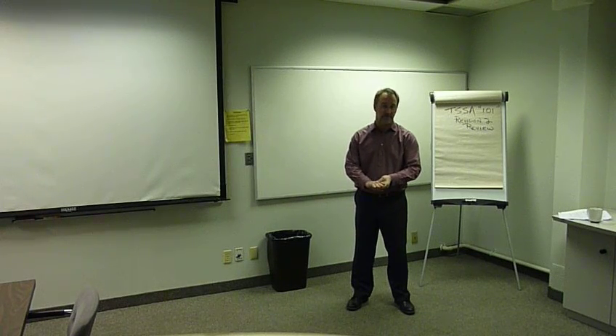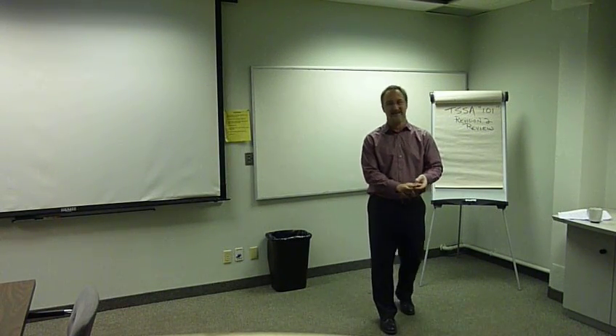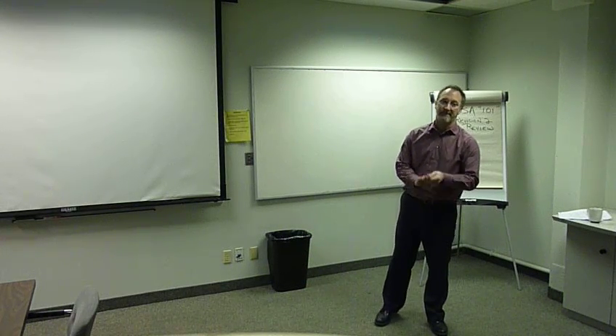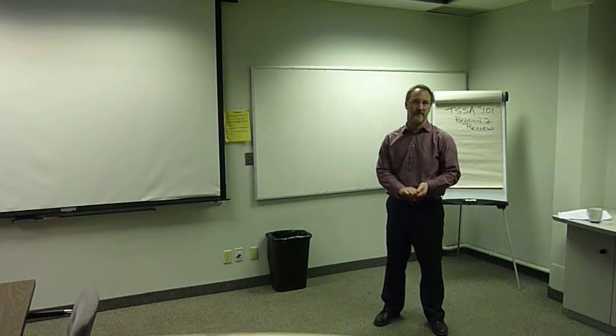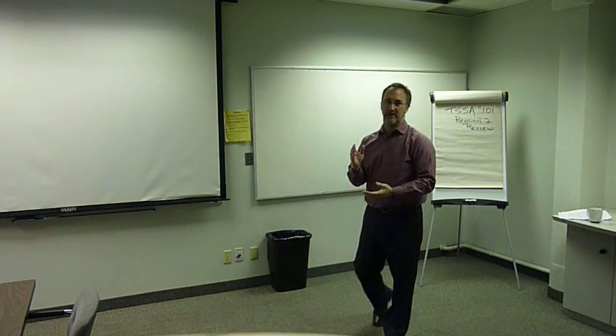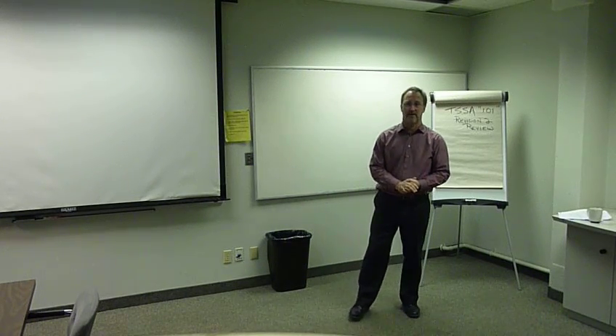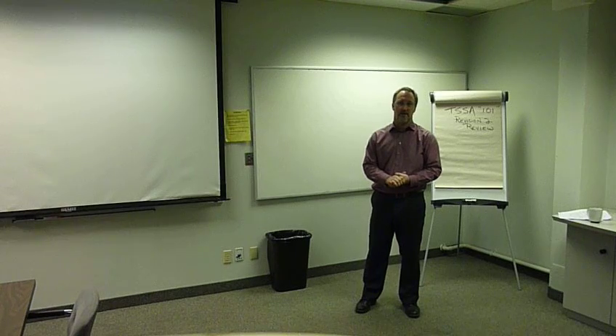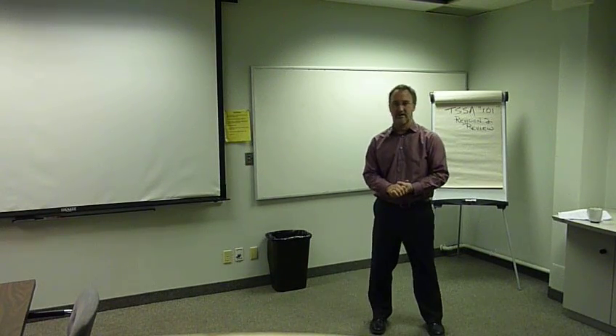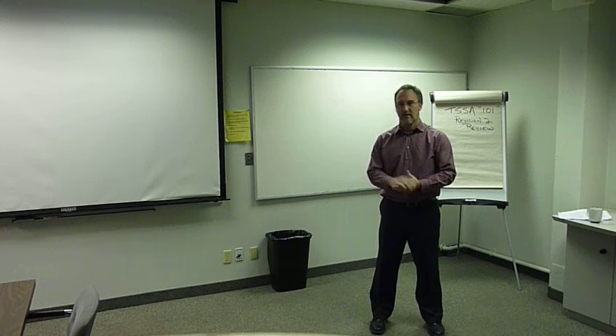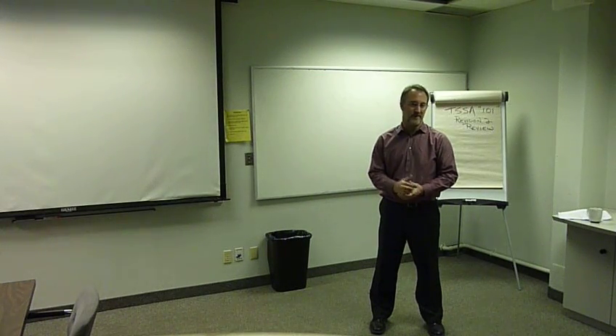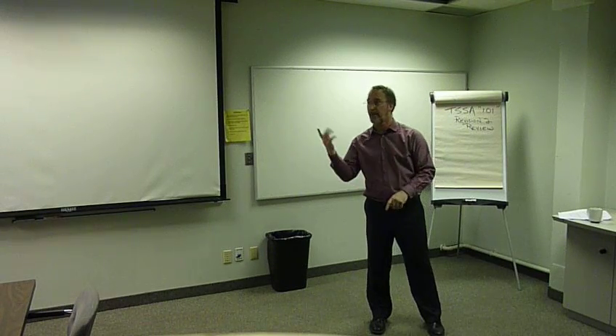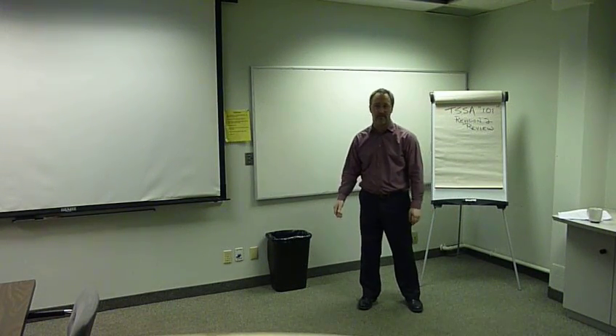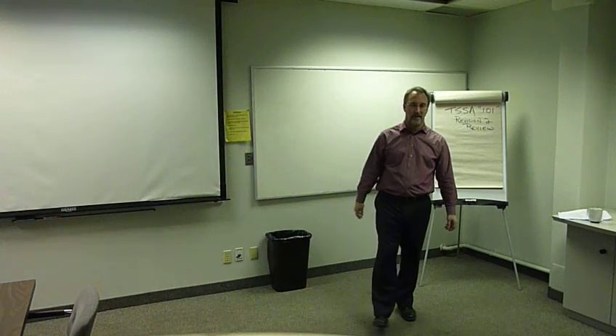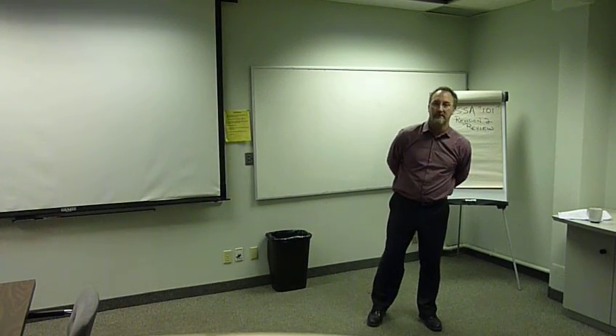Another area is inspections. The inspections are done by a TSSA authorized inspector. My advice to all of you is to get in touch with your inspector immediately when you start the project. They're very knowledgeable - you can talk to them for advice, for clarity, code rulings, all of these things. They're here to make your life easier. I would strongly recommend using them from cradle to grave on the job. If you have to do repairs, be they new repairs or existing repairs on devices or components within the facility already, these all must comply with the standard as well, and you can discuss that with your inspector.